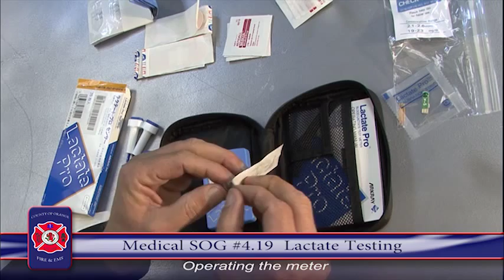So now we know that the machine is working within normal parameters, and it's now matching the strips that we're going to use. So those are the basic functions of this machine. As you can see, you don't need to turn the machine on. The machine activates as soon as you actually put a strip in it and turns off rapidly afterwards. So the process of actually doing a test is no different than the tests that you would normally see for glucose or anything else like that. There are some important things that you need to note about this, and we'll take one of these strips out and we'll do a test just as a demonstration.